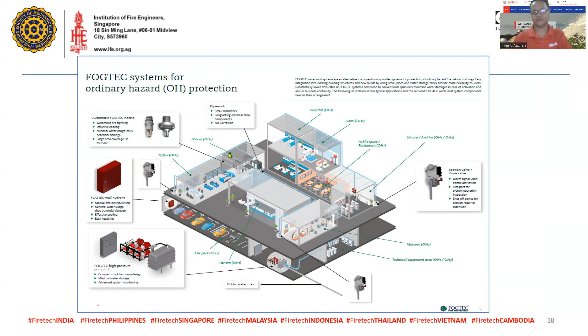And as I mentioned, it's a system that is composed of this high pressure pump. It is a compact modular pump, with minimal water storage and advanced system monitoring. And in each hydrant, it has manual fire extinguishing, minimal water usage, and effective cooling and easy handling. Its nozzle can cover a large area, up to 25 square meters per nozzle. That's how vast the area that this water mist system can cover. And the pipes, of course, because it's high pressure, are stainless steel, but with a smaller diameter compared to sprinkler. And also one of the good advantages is that it has no corrosion.